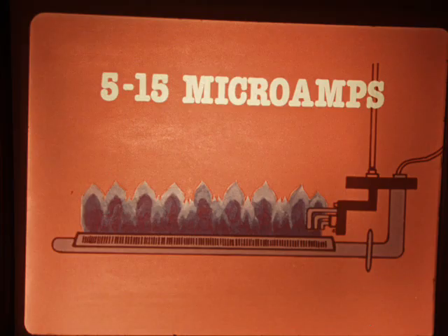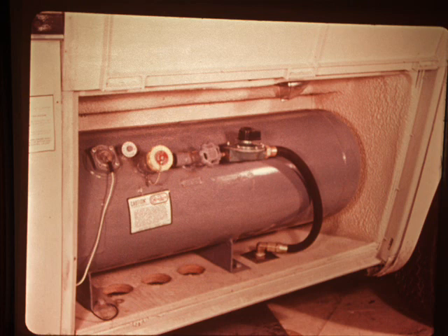Check the black lead to the flame sensor for continuity. Check the sensor electrode for proper position. The tip must be in the furnace flame. The current should be 5 to 15 microamps through the lead when the tip is properly positioned. A random shutdown can also be caused by air in the LP gas supply or a frozen regulator. Procedures for servicing the LP gas supply system are in your motorhome service manual.